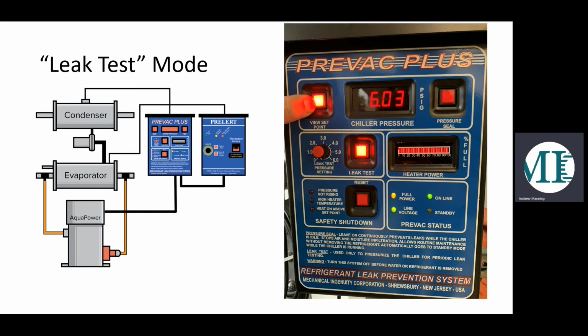We also have a leak test mode on the PREVAC. So just in order to leak test, you just press the button and dial up to whatever pounds you need for the leak test, and you can go about doing the rest of your maintenance on the equipment. So no need for portable pressurization systems, temporary water and electric hookups. It's all right here, hardwired, hard piped, and uses the same principles as the pressure seal mode, just cycles hot water through the evaporator and pressurizes the chiller.